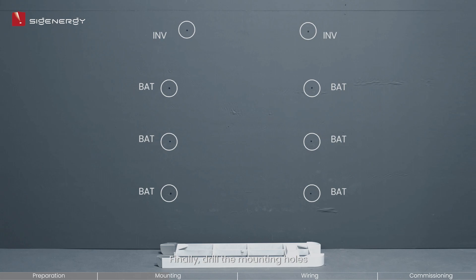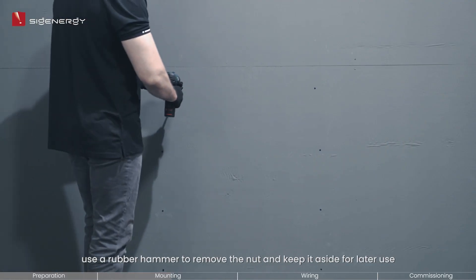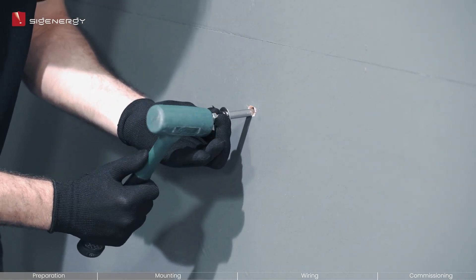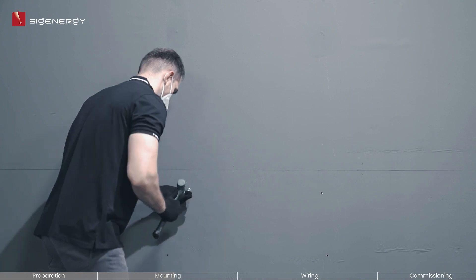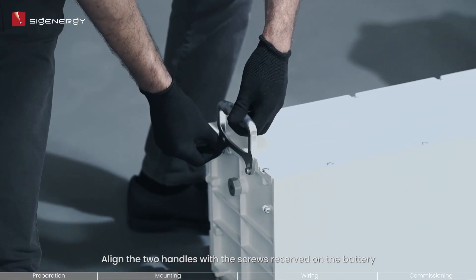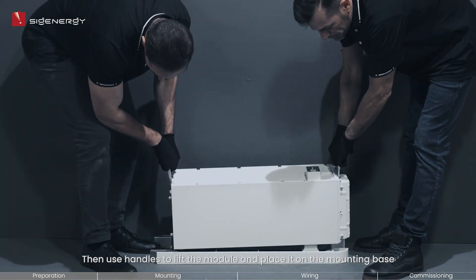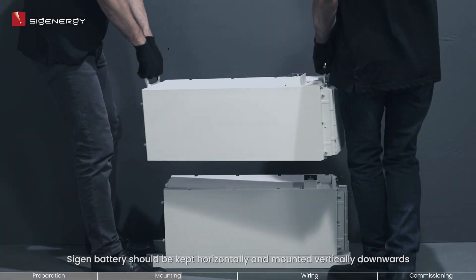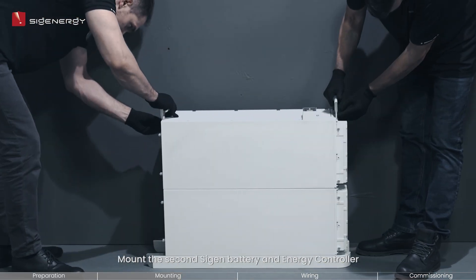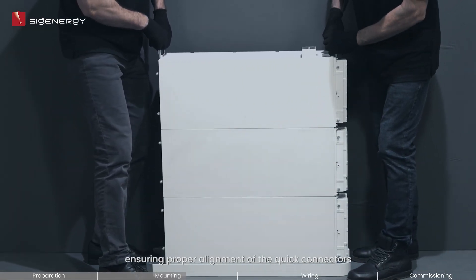Finally, drill the mounting holes. To ensure the correct installation of the 8 M8 expansion bolts, use a rubber hammer to remove the nut and keep it aside for later use. Align the two handles with the screws reserved on the battery, then use the handles to lift the module and place it on the mounting base. Mount the second Sigen battery and energy controller using the same procedure, ensuring proper alignment of the quick connectors.